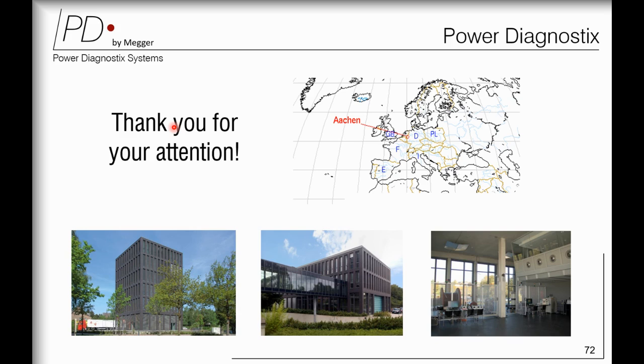One more question is from Mr. Abdul Rahim: for the portable monitoring system, how is calibration carried out at a GIS that cannot be shut down? For GIS, we don't need to take a shutdown, because calibration is not required for the UHF measurements. Calibration is a process you do for rotating machines like generators and for transformers, but we don't do calibration in GIS because it is a live condition.